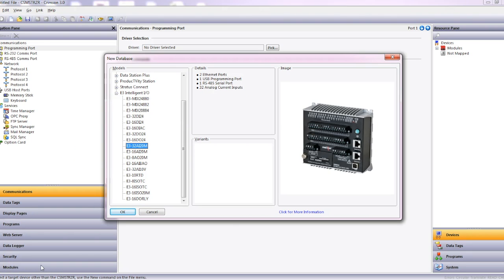All of which have two Ethernet ports, a serial 485 port, and a programming USB port. The Ethernet port is quite unique in that it comes as standard as 2 and it can be used on individual subnets or it can be configured to pass through as a standard switch, or alternatively we can set it up as a redundancy port so there will be a ring between all the different I.O. points on a network.